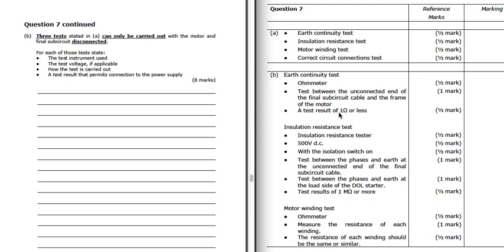Earth continuity, we're looking for that 1 ohm or less using an ohm meter. And with the insulation resistance, we're looking at 1 mega ohm or more using an insulation resistance tester on 500 volts DC.